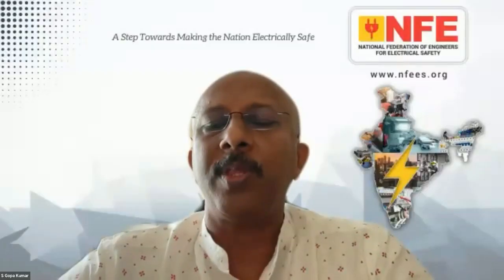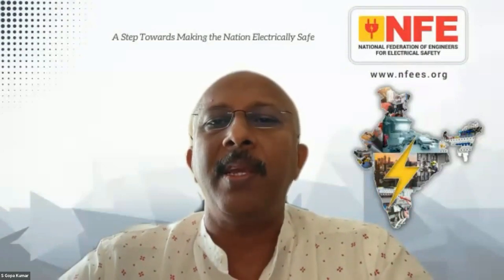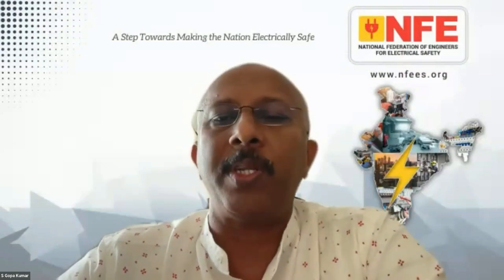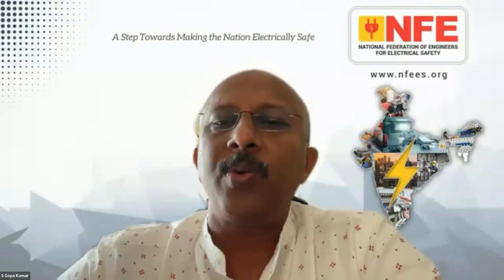Solar earthing has different techniques explained so that a fault on the DC side can be handled and shock protection is achieved. You have to look into that. Generally, I have observed, because I have been part of supplying high voltage switchboards to various solar projects, maybe more than 300, 400 installations I have seen. The general practice in solar installations is that the inverter transformer LV side neutral is not connected to earth, to avoid circulating currents, because these inverters generate a lot of harmonics, and to avoid the triplen harmonic circulating currents. People say, I am surprised why you are not grounding the neutral. They say we want to avoid circulating current.